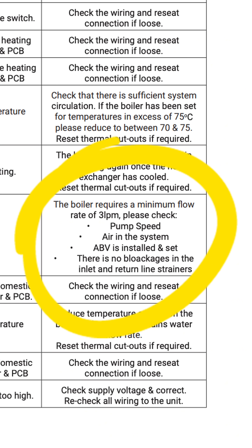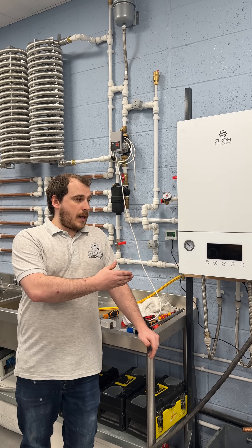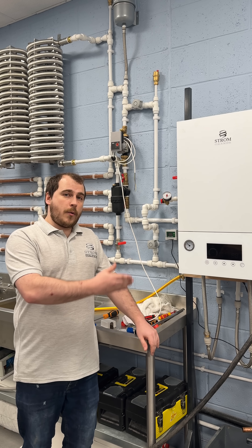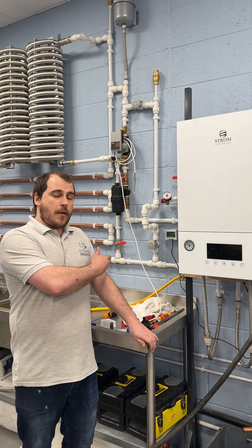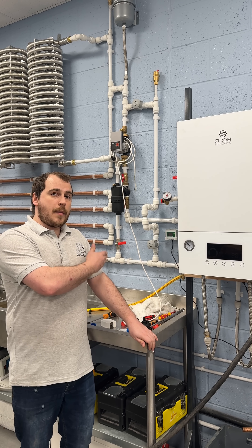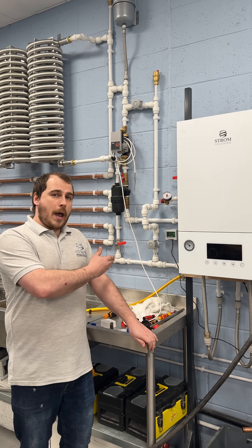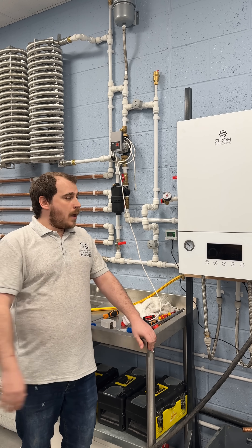We need to ensure that we've always got a flow rate of 3 litres a minute or above within the heating system, otherwise we see this E5 error code. I'm going to reset this error code and then we're going to demonstrate on this heating system how and why it would trigger.